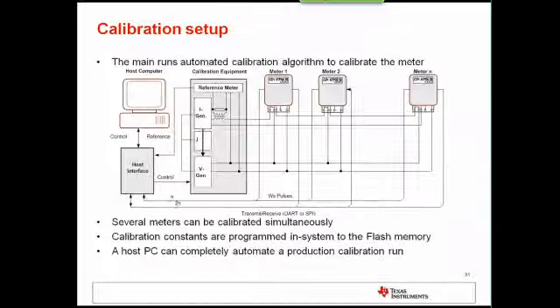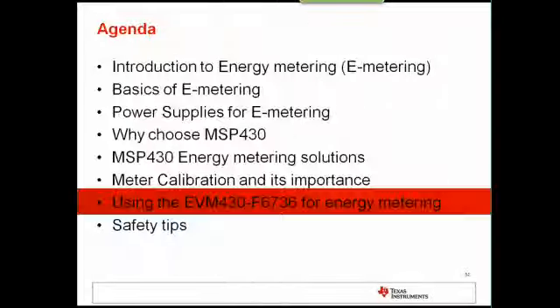A host PC can completely automate a production calibration run. In this scenario you would have a host computer that controls a host interface to have a source generated to produce voltage and current. Based off of the voltage and current, the meters would calculate power and output pulses. The reference meter could use the pulses to determine what the error is and feed it back to the host interface for any actions to be taken by the users.